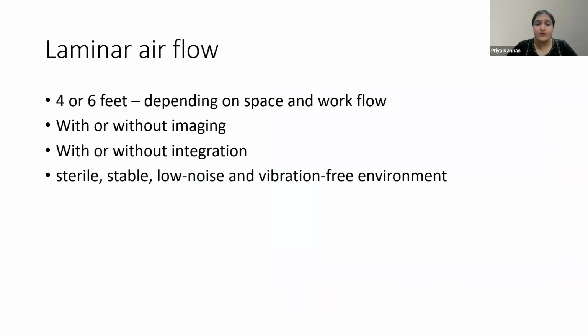Then the laminar airflow, which is mandated by our law to have, but there are countries, there are labs in our country also which do not use a laminar airflow, but by the law, we are mandated to have a laminar airflow. You can choose to have a 4 feet or 6 feet. The 2 feet laminar airflows are only for andrology. You need to have a 4 feet or a 6 feet for the embryology, depending on the space that you have and the workflow that you need. You can also have more than one laminar airflow, depending on your workflow. You can have it with or without imaging. That is, with or without the screen for everyone to see, with or without integration, as I showed you.